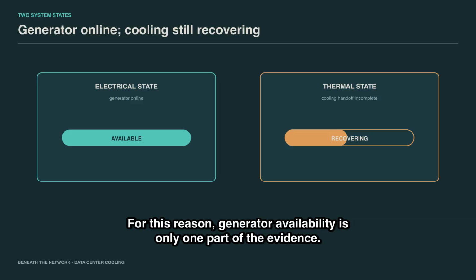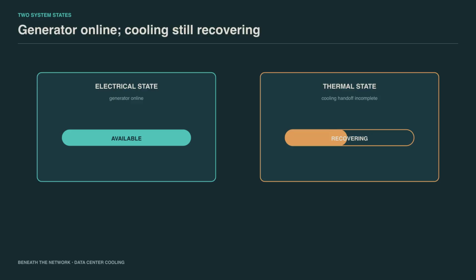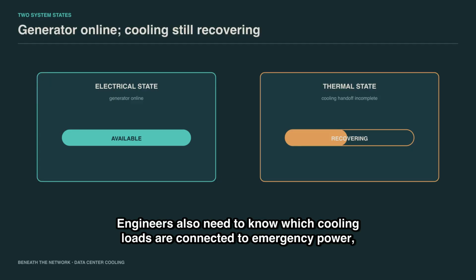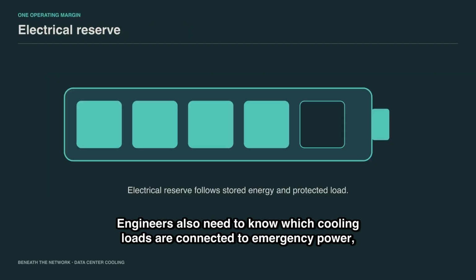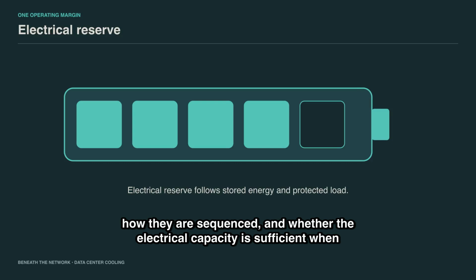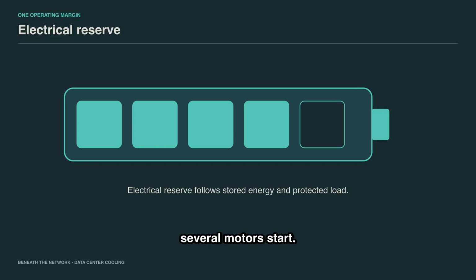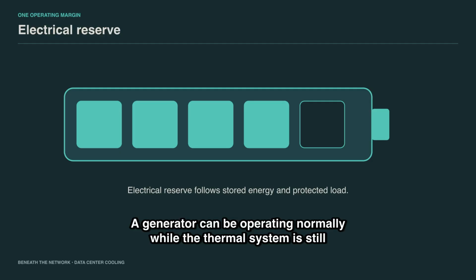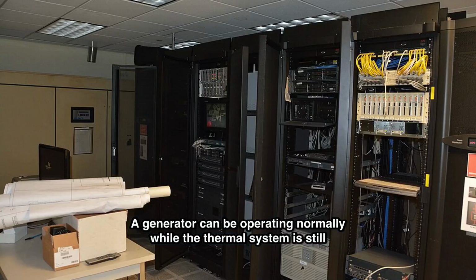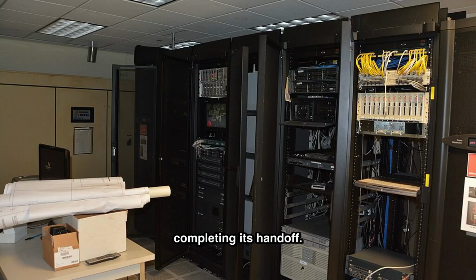For this reason, generator availability is only one part of the evidence. Engineers also need to know which cooling loads are connected to emergency power, how they are sequenced, and whether the electrical capacity is sufficient when several motors start. A generator can be operating normally while the thermal system is still completing its handoff.